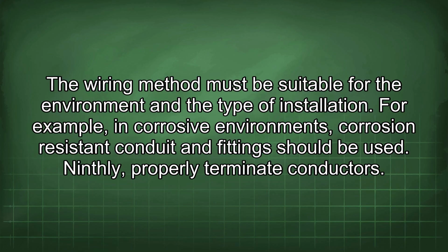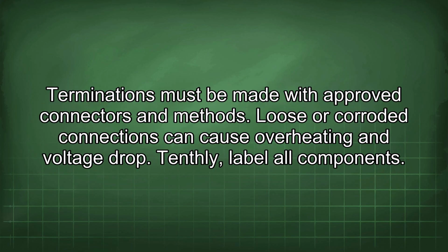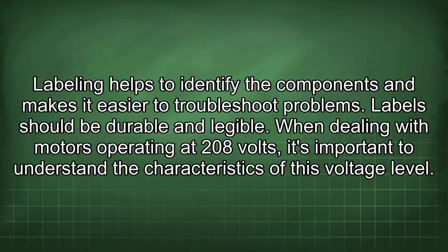Ninthly, properly terminate conductors. Terminations must be made with approved connectors and methods. Loose or corroded connections can cause overheating and voltage drop. Tenthly, label all components. Labeling helps to identify the components and makes it easier to troubleshoot problems. Labels should be durable and legible.